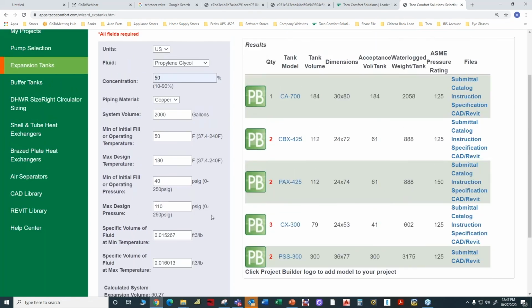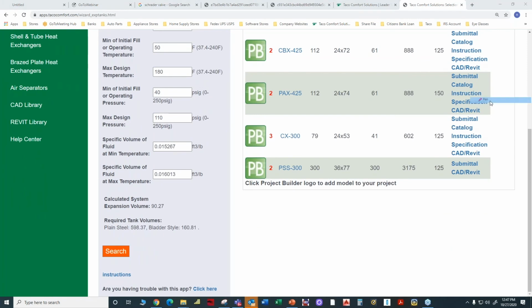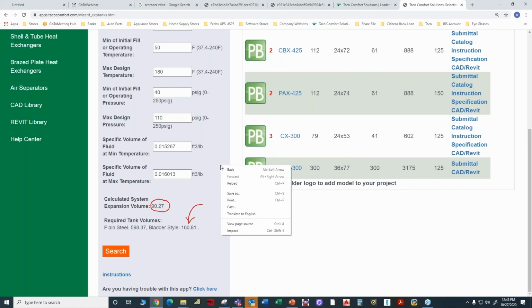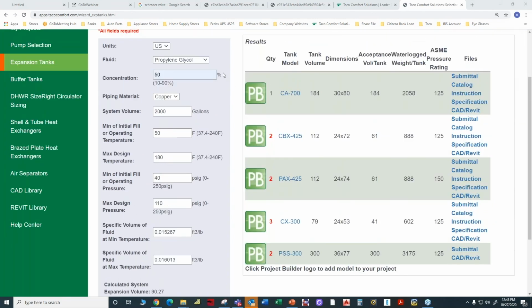Now look what happens. The expansion, instead of being 53 gallons, is approximately 90 gallons, just over 90 gallons. And the tank would be required to be 160. Well, remember, you only have 119 gallons in there. Because the tank is physically smaller than what's required in this selection, when the fluid heats up, it'll open the safety relief valve, and you'll have water, in this case propylene glycol and water, all over the place. So if you don't change any of the sizing but simply change the fluid characteristics, you run into a situation where the tank is too small if you put in propylene glycol at 50%.